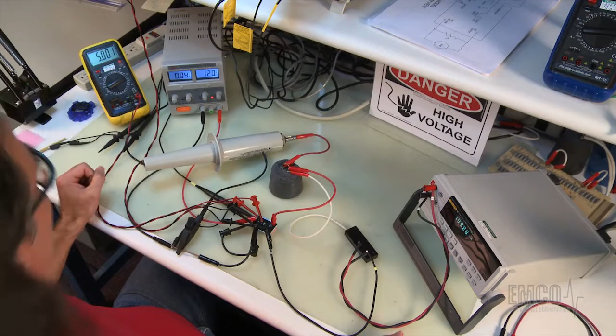So now I can connect my load. In this case, I just have a resistive load set up to the full load output of the CA20P, which ends up being 4 megaohms. And as I mentioned earlier, we need to make sure the power and voltage rating of the resistors used for the load are capable of withstanding the voltage and the power that the unit will provide. In this case, it's 1 watt of power and 2,000 volts, so I had to use fairly high voltage resistors here for my dummy load.